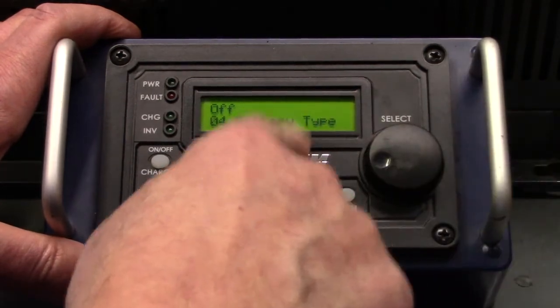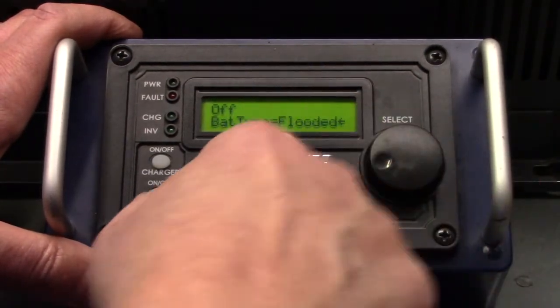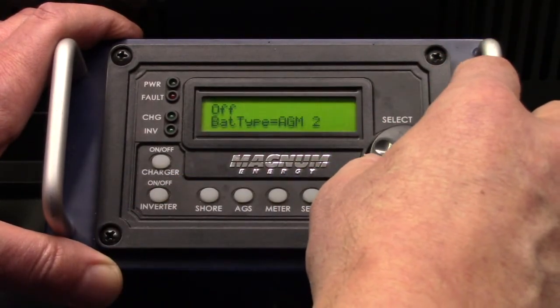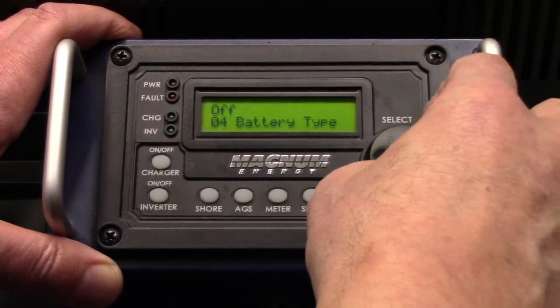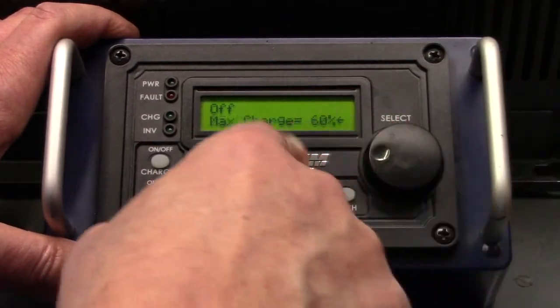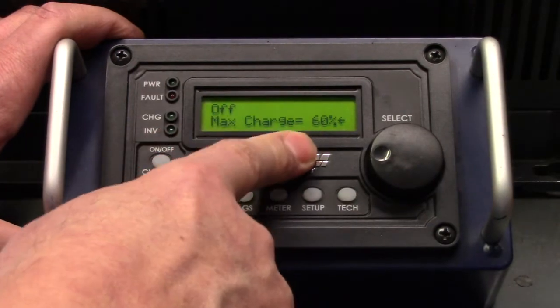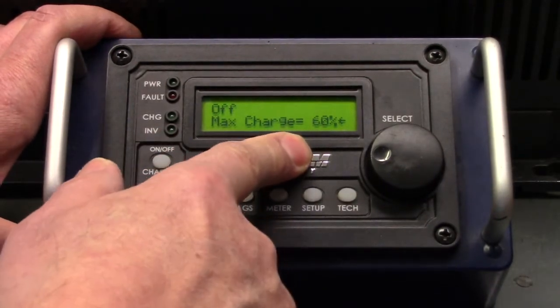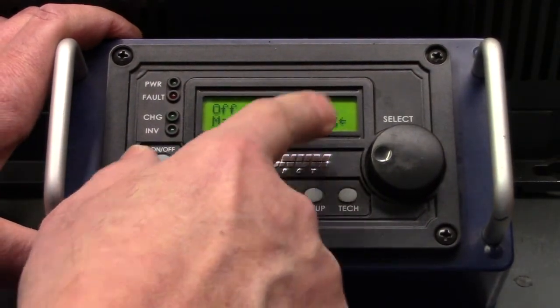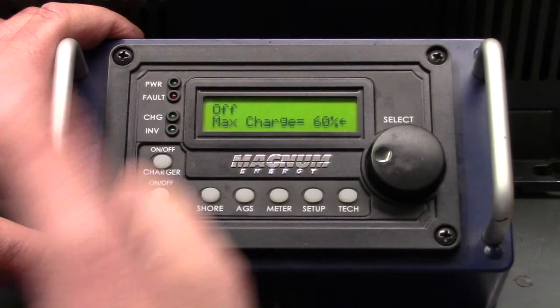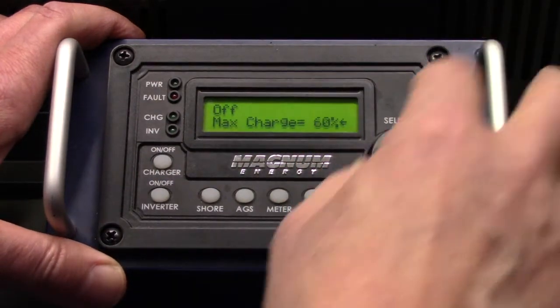Battery type, again, this one is important. Got to make sure that's set right: flooded, AGM, or whatever type you have. Charge rate, that's an important one too. If you have problems blowing your shore power breaker out there a lot, you may want to turn that one down if you don't need to charge those batteries so fast.